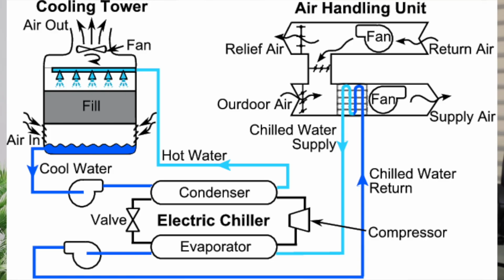Number 7, how does a chilled water system operate? It's a very important question. The heart of a chilled water system is the chiller. A lot of companies are making chillers, even Carrier. One end of the chiller is connected to the cooling tower, and the other end of the chiller is connected through a heat exchanger, then to your chilled water pump room system. You got my point.